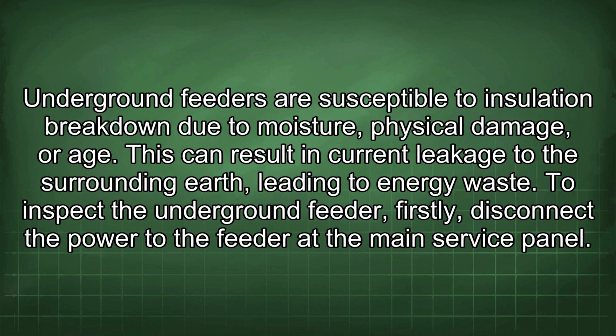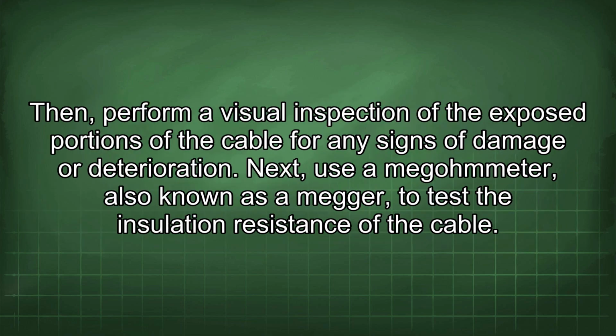Underground feeders are susceptible to insulation breakdown due to moisture, physical damage, or age. This can result in current leakage to the surrounding earth, leading to energy waste. To inspect the underground feeder, firstly, disconnect the power to the feeder at the main service panel. Then, perform a visual inspection of the exposed portions of the cable for any signs of damage or deterioration. Next, use a megohmmeter, also known as a megger, to test the insulation resistance of the cable.